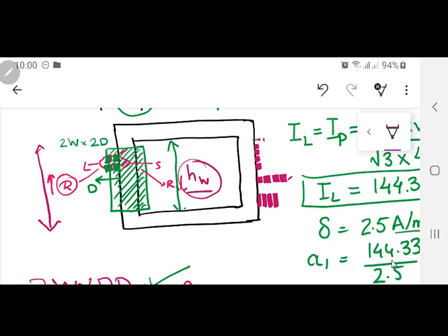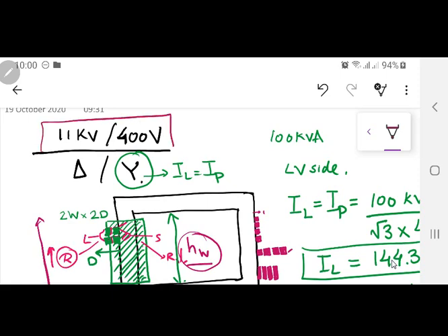Okay. Good, one thing very important I want to ask you, because now in that lab we have a testing facility also. Now what that testing facility does, listen to this very carefully. Whenever an 11 kV / 400 volt transformer comes over there for testing, according to international standard, the 400 volt winding should be able to withstand a spike of approximately 600 volts, and this is a switching spike. Whenever I am talking about a switching spike, it is the same spike as when you switch on the piano buttons or switch buttons over there, and instantly you see a little spark taking place.